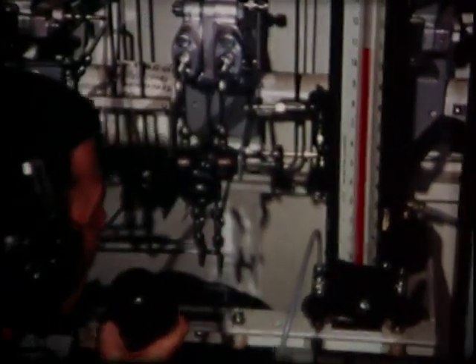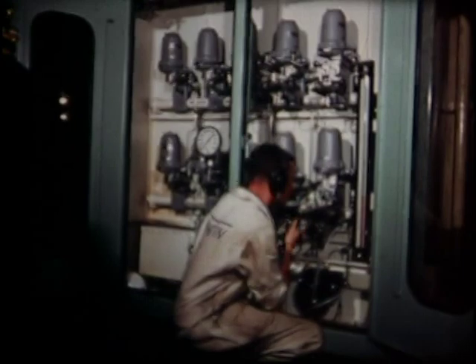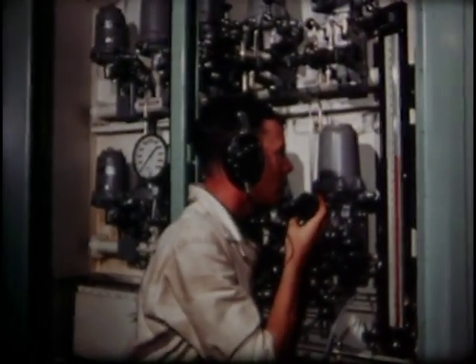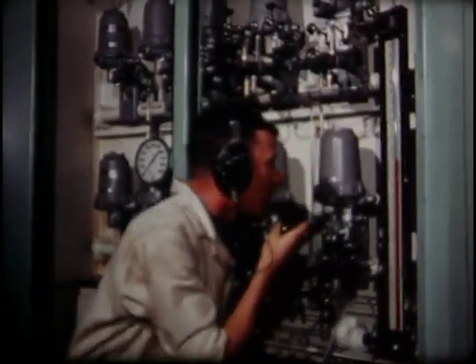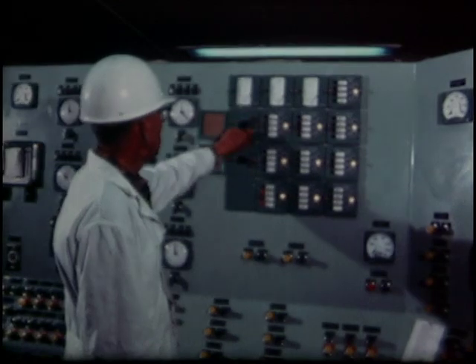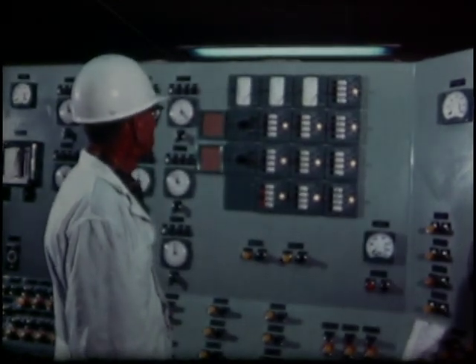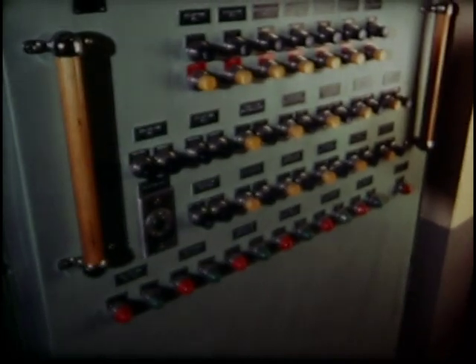For example, controlled and varied pressure was applied to the pressurizer pressure transmitter, and the correct response of the pressurizer pressure indicator was verified. Similar means were employed to test other instrumentation and alarm systems, the temperature monitoring system, the annunciator panel, and alarms on the waste disposal panel. The work thus far laid the groundwork for testing equipment and larger systems.